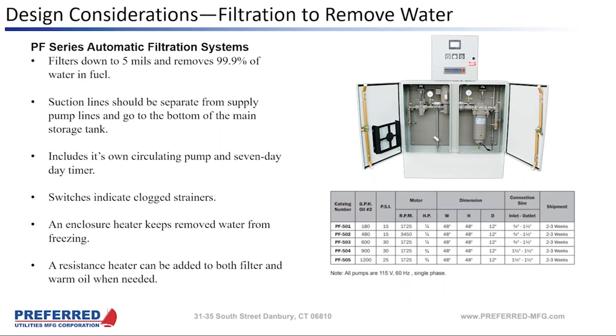And if you have a polisher and you do a bottom sample in your tanks and you're still seeing water, then I would set the polisher up to run another day. If I've already got it going 8 hours on Monday, I'll set it up to go 8 hours on Tuesday, because water in the bottom of the tank indicates that we're not running the polisher enough. And if you're not seeing that water coming out with your polishing system, that's probably something you need to take a look at.